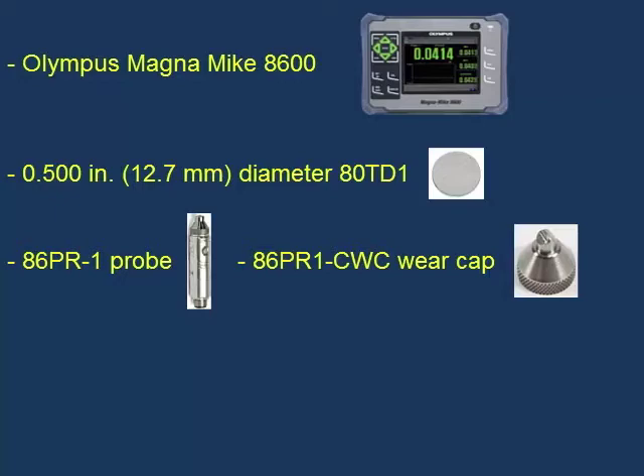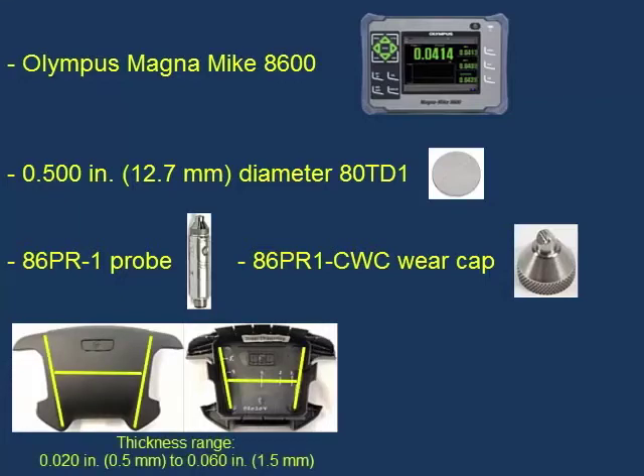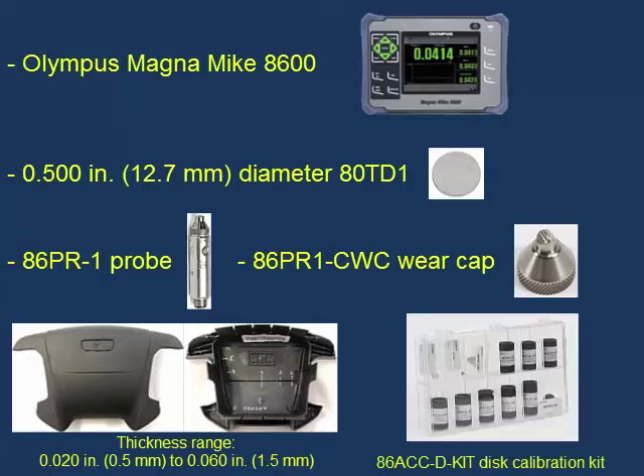We will then use the disc target to measure the thickness of tear seams on an automotive airbag cover. The thickness of the tear seams range from approximately 0.020 inches or half a millimeter to 0.060 inches or one and a half millimeters. We will be using the 86ACC-D-KIT, which includes the chisel wear cap, target discs, disc on fixtures, and reference standards designed to be used with the disc targets.